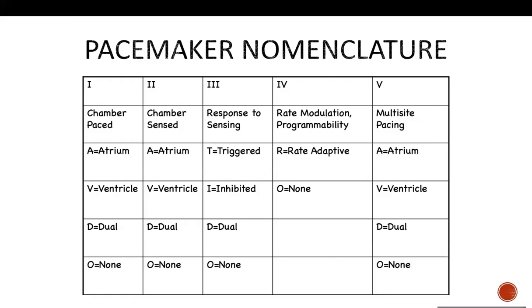So the defibrillator has defibrillation and has pacing. But if you want to avoid inappropriate shock during the procedure, we're going to have to change the shock setting, not the pacing setting. Pacing is only for pacing.